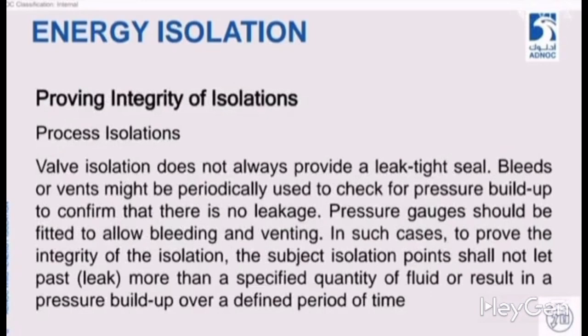Proving the integrity of isolation, how valid and effective our isolation is, what process do we use to check and ensure its integrity. So first let's talk about process isolation. Valve isolation does not always provide a leak tight seal. Any valve isolation we have is not always 100% seal tight. We need to timely check the pressure build-up to ensure there is no leakage inside. Pressure gauges should be fitted to allow for the monitoring and venting. For process isolation, where we need to hold pressure and maintain it, we will need to install pressure gauges to ensure the integrity of the isolation.